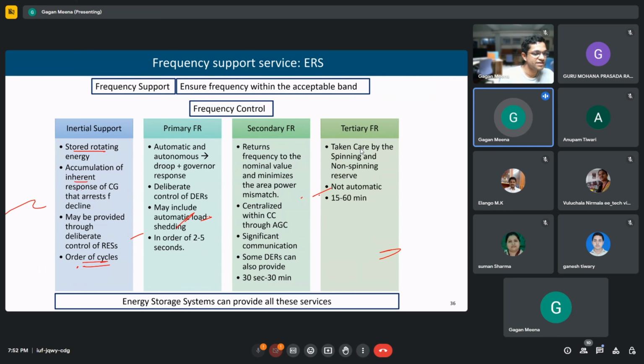It is the accumulation of the inherent response of conventional generators that arrests the frequency decline. So it can be provided by virtual inertia also. This is on the order of cycles. One cycle is 20 milliseconds, so within 1-2 cycles it can work. Then, if the frequency is not arrested by this inertial support, that means the deviation is much more, and we have to move to the primary frequency response. It is also automatic. It is based upon the droop control and governor response. Based upon the droop characteristics, the load increase or decrease will be distributed among all the parallel connected generators, and the frequency will be restored to a common value.